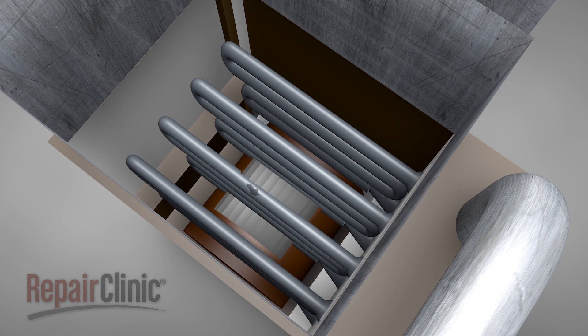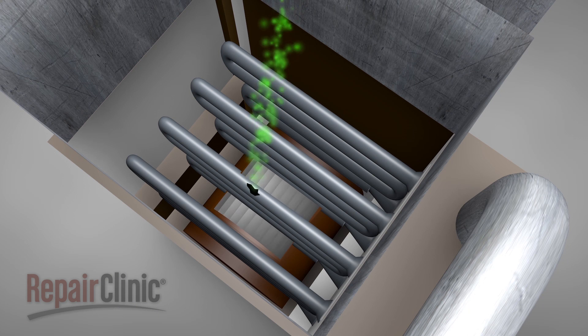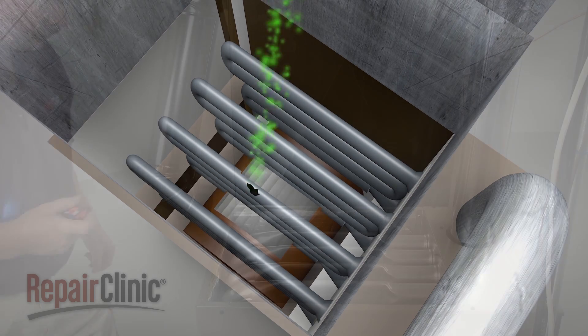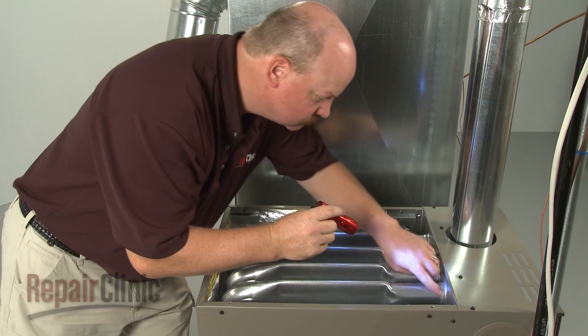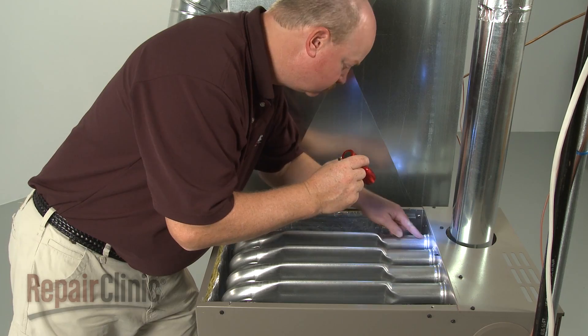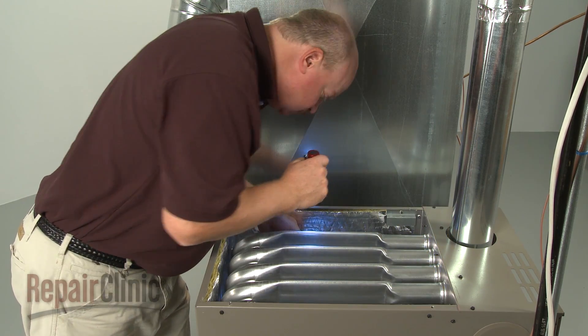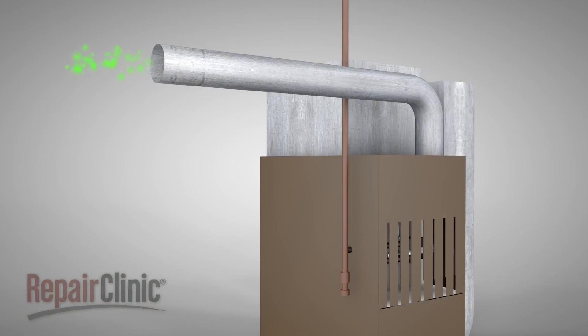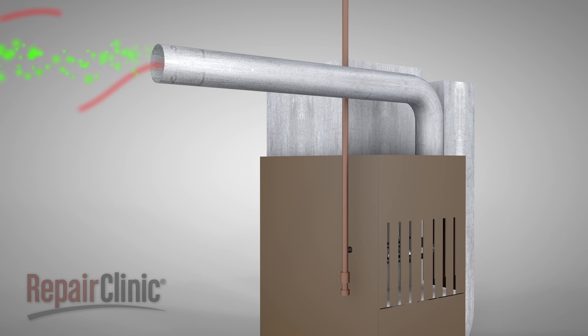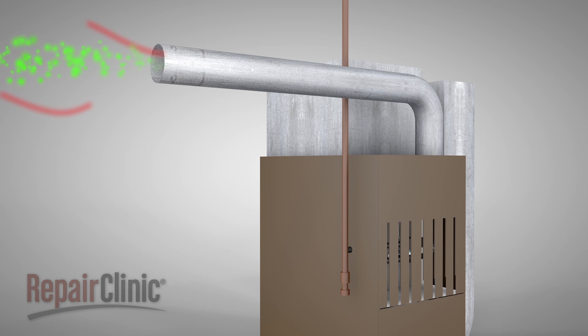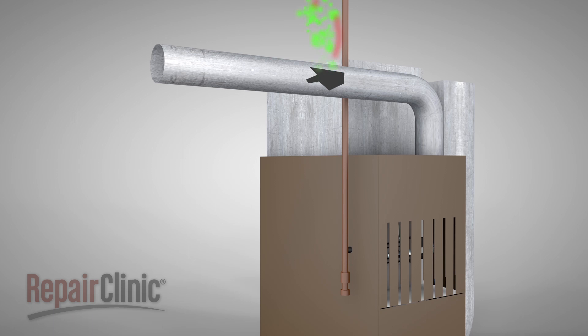Over time, heat exchangers may crack and cause carbon monoxide to leak into the air being circulated throughout the home. Since carbon monoxide poisoning can result in death, we recommend that only experienced professionals repair or replace damaged heat exchangers. Under normal working conditions, the furnace will exhaust the carbon monoxide through a flue or exhaust pipe to the outside of the home. If the flue or pipe breaks, cracks, or rusts, carbon monoxide will contaminate the air.